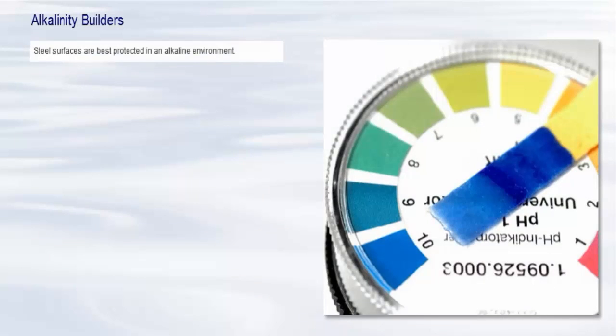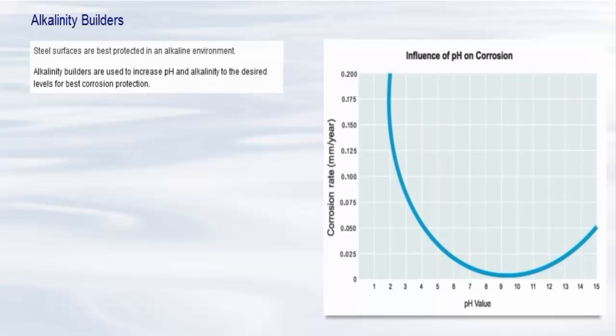Steel surfaces are best protected in an alkaline environment. Alkalinity builders are used to increase pH and alkalinity to the desired levels for best corrosion protection. Alkalinity builders also help with scale control in alkali phosphate treatment programs. The alkalinity of the water also acts as a buffer, a property that will absorb pH changes if acid components are introduced and maintain an alkaline pH.